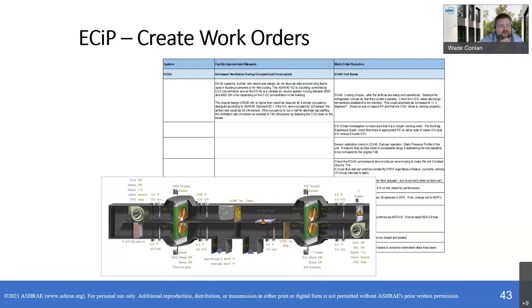This was the old ASHRAE headquarters, where we talked about increased ventilation and then other items we found, right? As we discussed this unit, there are energy things in here and operational things, like this had separate condensing units for each circuit and a couple of them were failed. So we wrote, hey, you need to get the deferred maintenance, you need to get the facilities maintenance team out there to get those up and working because we need to make sure that we've got the outside air.